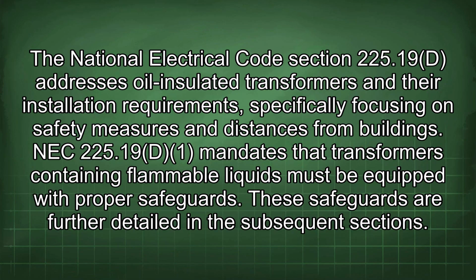The National Electrical Code Section 225.19d addresses oil-insulated transformers and their installation requirements, specifically focusing on safety measures and distances from buildings. NEC 225.19d mandates that transformers containing flammable liquids must be equipped with proper safeguards. These safeguards are further detailed in the subsequent sections.